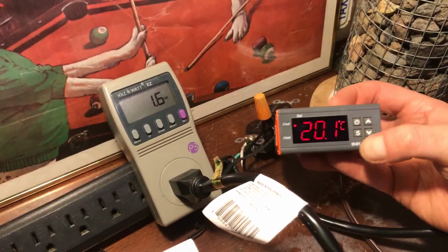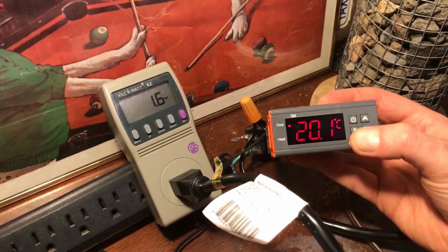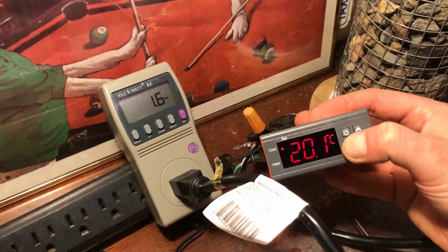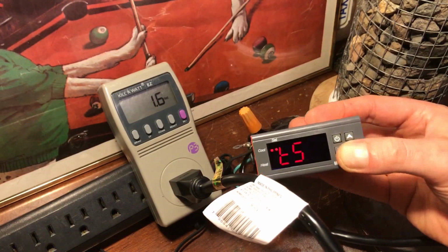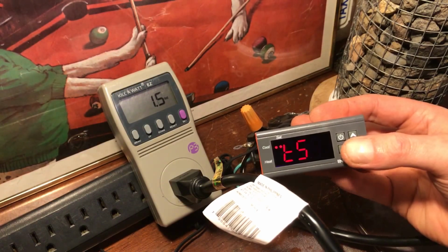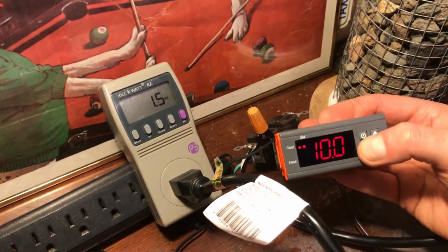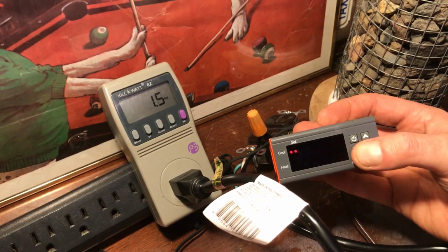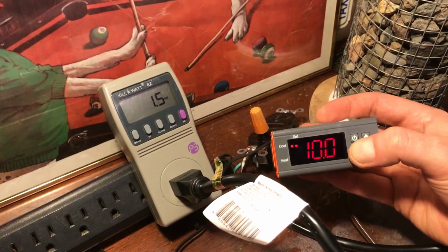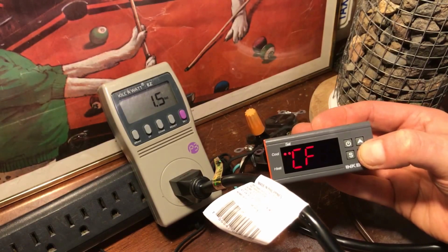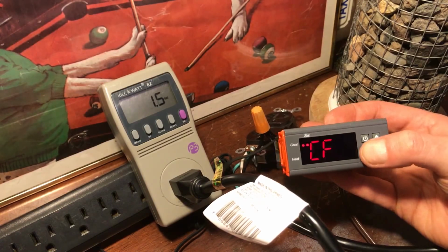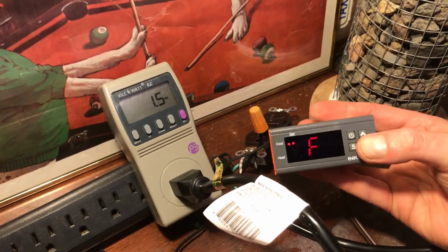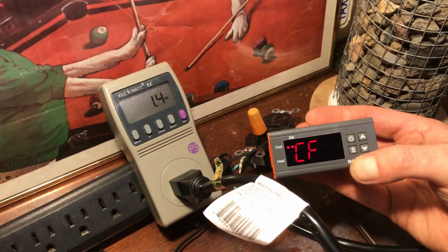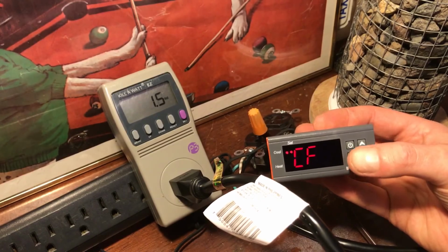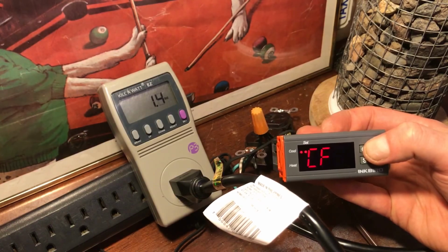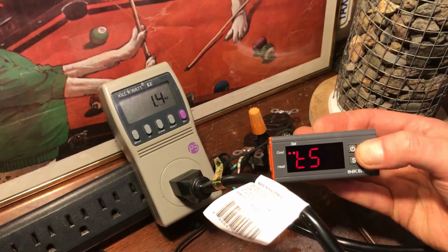So let's go ahead and check that out. So we hold down the S to get into the menu. So TS is the temperature set value, so we press S again to go into that. And it's set at 10 Celsius, so let's switch it to Fahrenheit real quick. CF, F, and then S. And this one is kind of annoying, you have to hit S and then exit out of the menu with the on-off button for it to save.